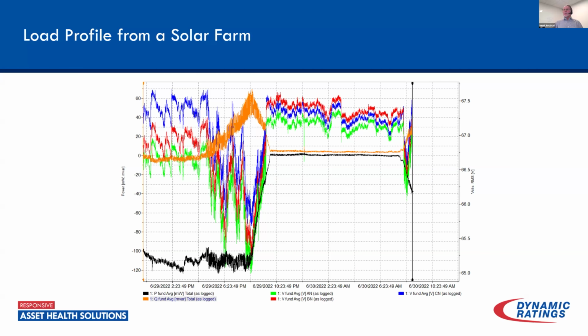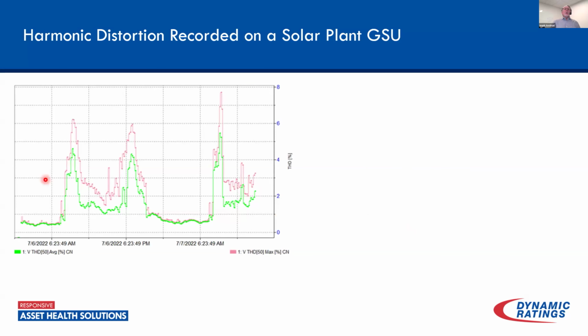Now, that's only where it starts. So we talked about the voltage profile and things like that. We'll get into a little bit, but here we're also talking about the harmonic impact and the impact that the harmonics can have on that insulation. So here we're looking at the total harmonic distortion. This is the total harmonic voltage distortion. And IEEE and IEC are pretty much recommending about a 5% maximum total harmonic distortion. But here, looking at the averages, we're pretty much close to that. But this is about a 10-minute average.